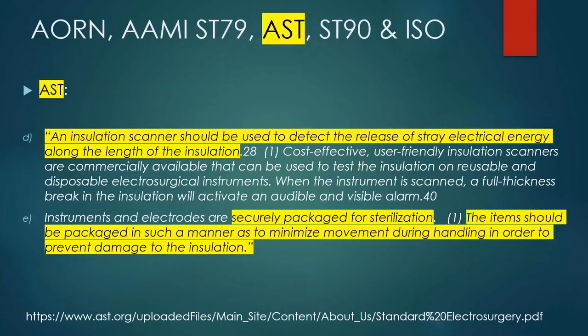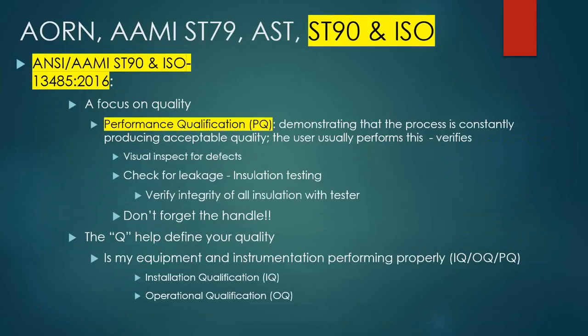Instruments and electrodes are securely packaged for sterilization, and the items should be packaged in such a manner to minimize movement during handling in order to prevent damage to the insulation. Exactly what Sharon said, and we're actually going to have some examples of that coming up.